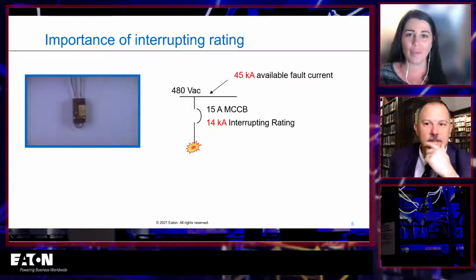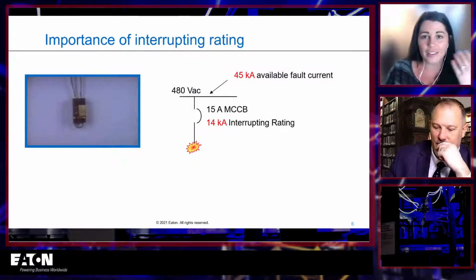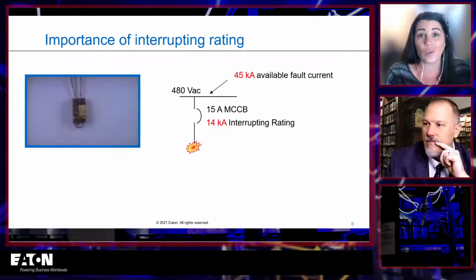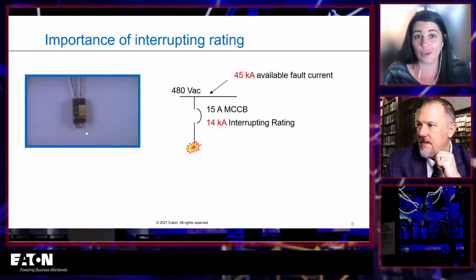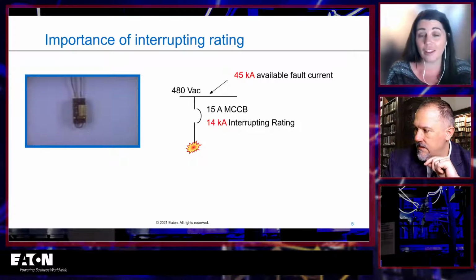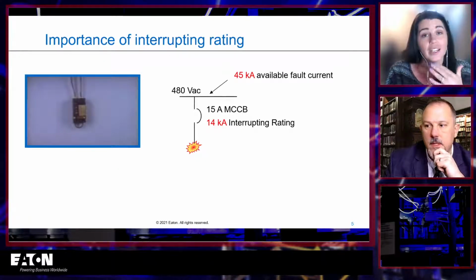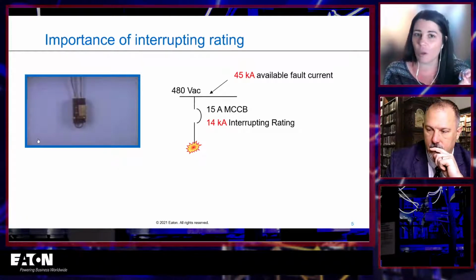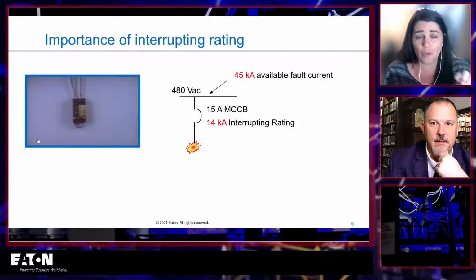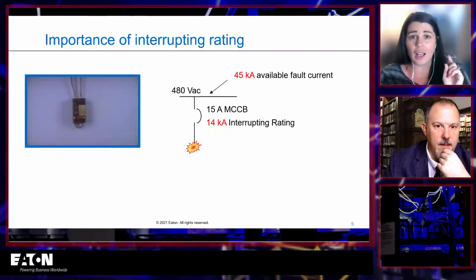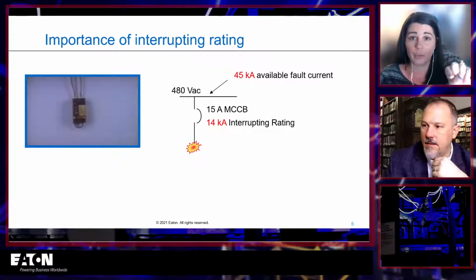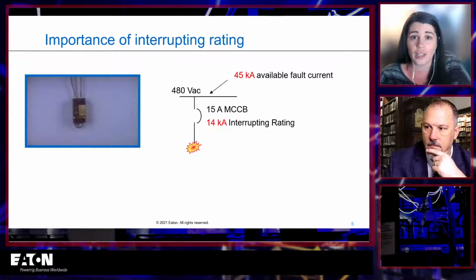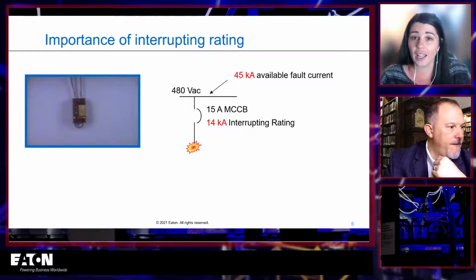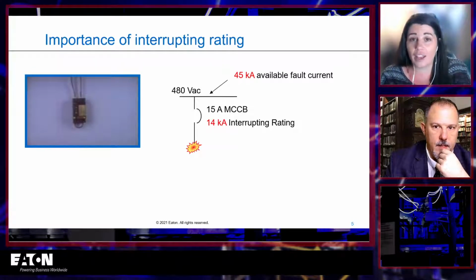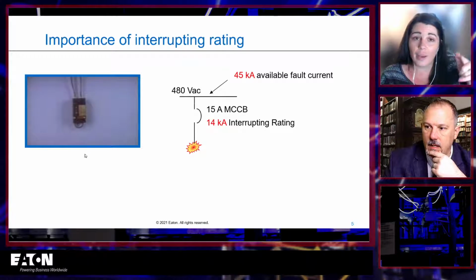Oh, here we go. Everybody's favorite part of any Bussmann presentation, an example of when we don't have enough of a specific rating. So this is an example of not enough interrupting rating. That's just to demonstrate why it's so important. So, 480 volt system. This is a 15 amp, 2-pole molded case circuit breaker. We shorted it right there on the load side terminals. 14 kA interrupting rating, 45,000 available fault current, and go ahead, play that video.